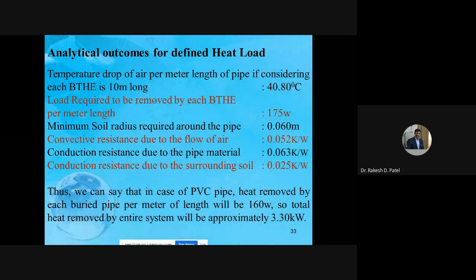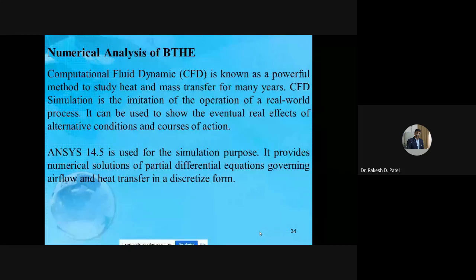The temperature drop of air per meter length of pipe, considering each buried tube heat exchanger is 10 meter long, is 40.80 degrees centigrade. The heat required for removal by each heat exchanger per length is 175 watt. The minimum soil radius required around the pipe is 0.06 meter. Then the convective resistance due to the airflow, pipe material and surrounding. Thus we can say that in the case of PVC pipe, the heat removed by each buried pipe per meter of length will be 160 watt. So the total heat removed by the entire system will be approximately 3.3 kilowatt. Now, numerical analysis.